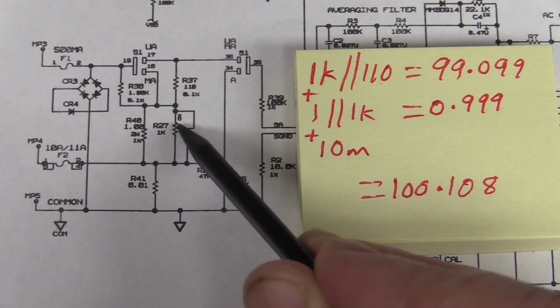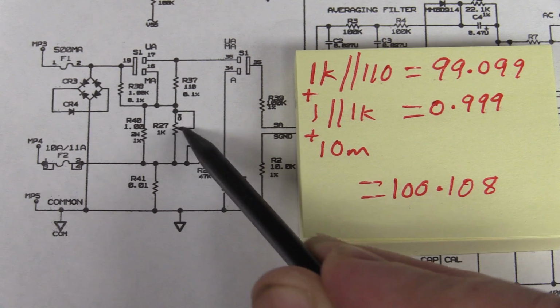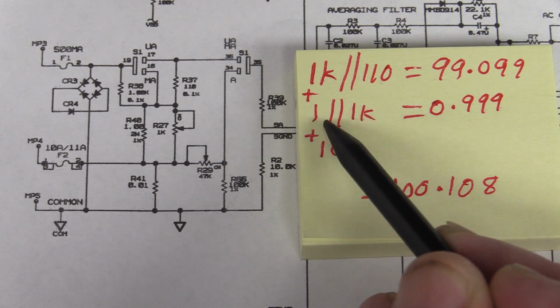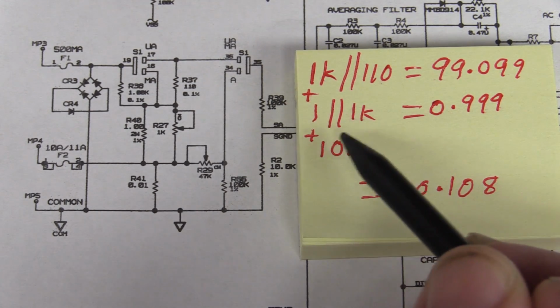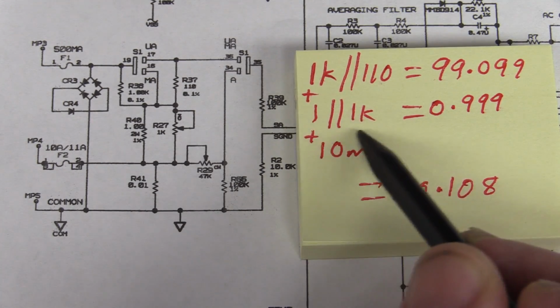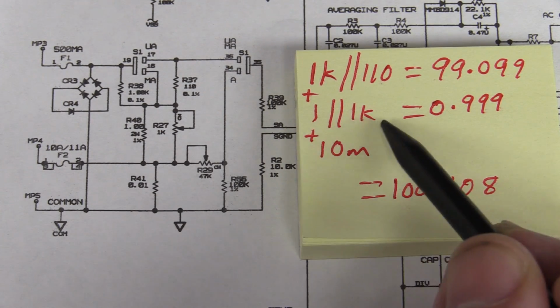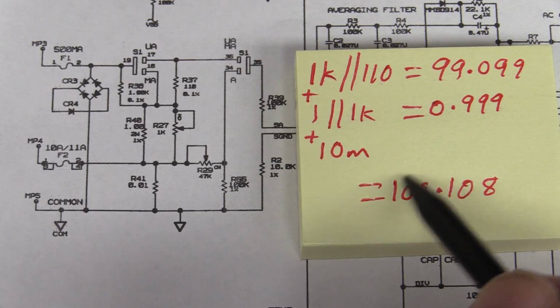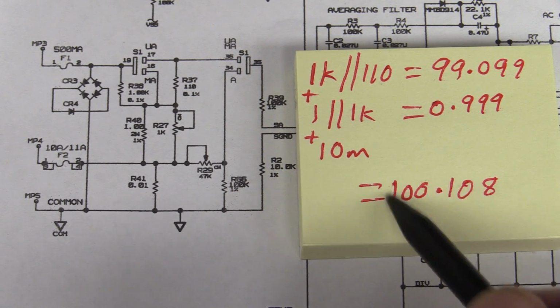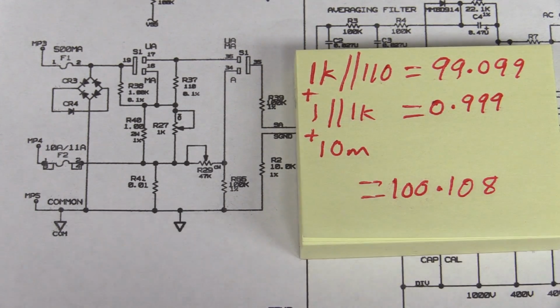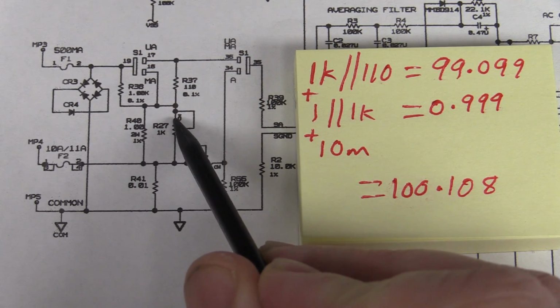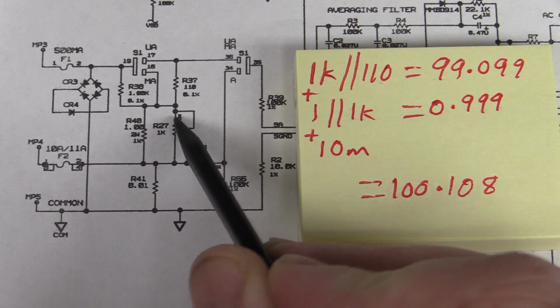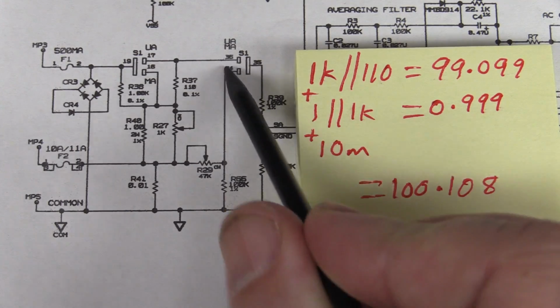So obviously they have to trim this 1K here—it's going to make a difference. They want that to be bang on, because this has no software compensation at all. So they want to trim this value right down to exactly bang on 100. So that trim pot will actually affect both the milliamp and the microamp ranges.